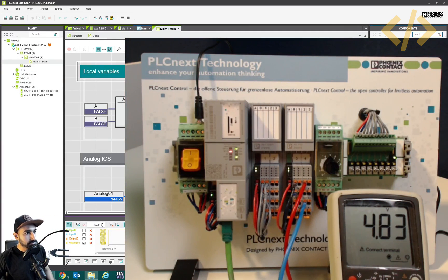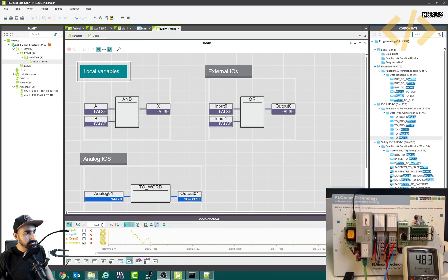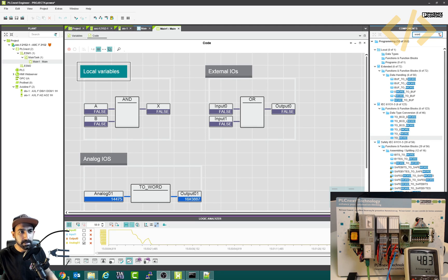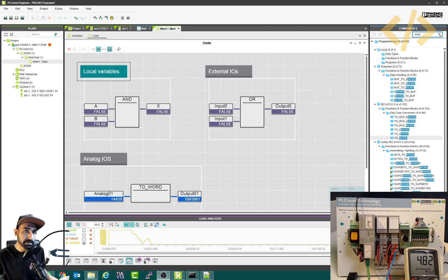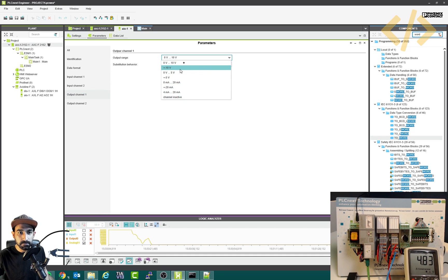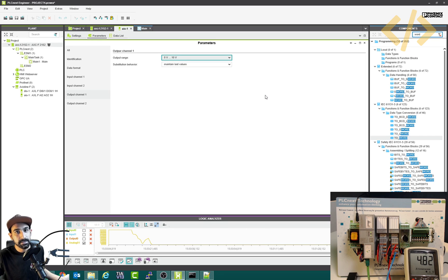That's how you can monitor your analog output with a multimeter by connecting the two terminals, or you can connect an analog actuator to the PLC to receive the voltage. This PLCnext trainer has two analog inputs and two analog outputs. Analog outputs are currently set at zero to ten volts. In the output channel one parameters, it can be plus-minus ten volts, zero to five volts, or current — you have both analog output voltage and current possibilities.